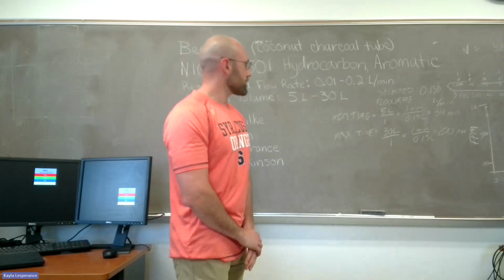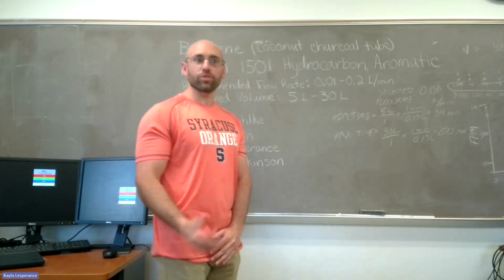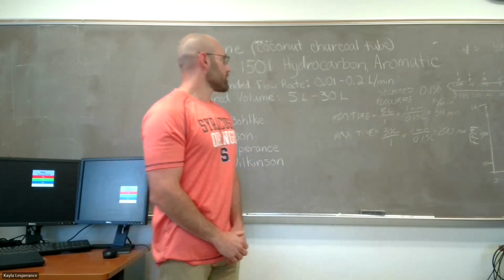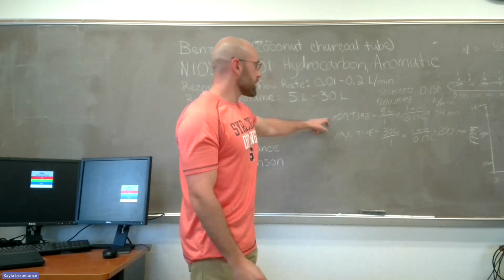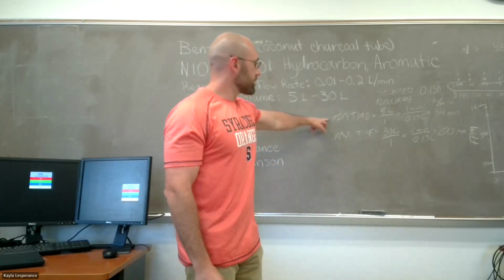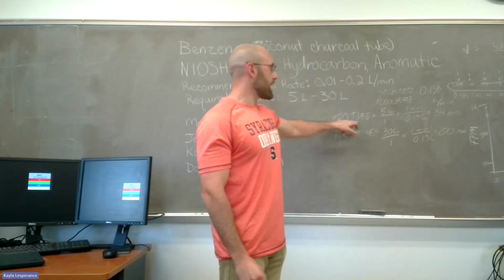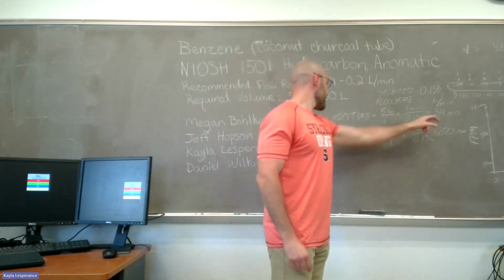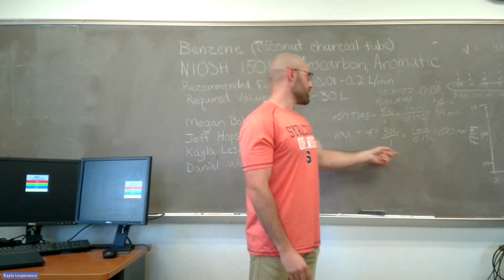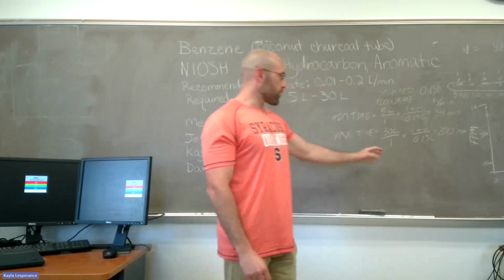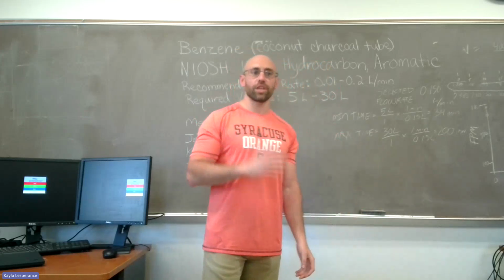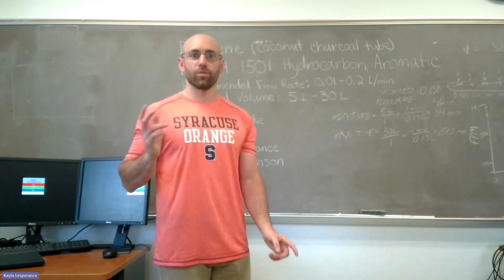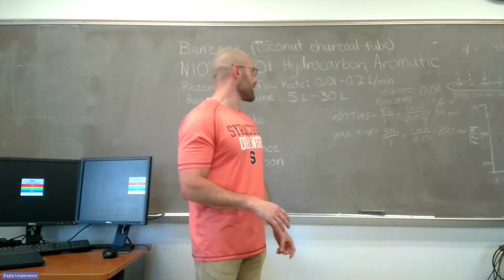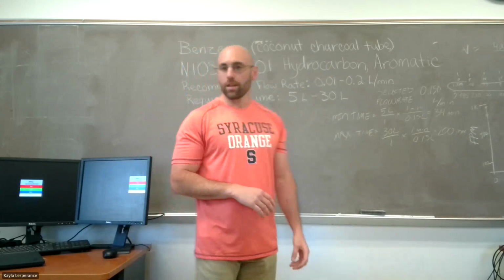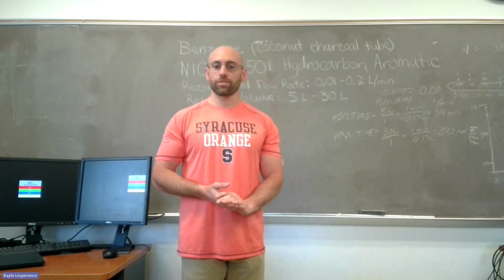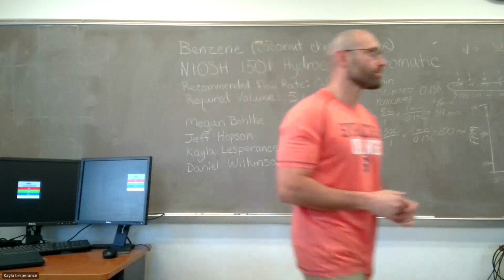It is best practice to ensure that we don't sample for too long or not long enough. So we have done some calculations to ensure that. With our minimal volume, our minimum time is 34 minutes, and our max time for 30 liters is 200 minutes. Before 200 minutes, we will have to change the charcoal tube to another one if we're going to continue sampling that day. Megan is going to talk next about equipment and calibration.